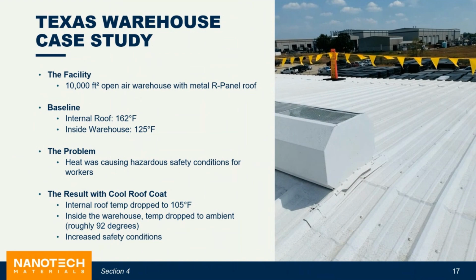Air temperature isn't what makes the warehouse miserable. A 162-degree Fahrenheit ceiling radiates onto workers the way a broiler does. You feel it on your head and your shoulders, regardless of what the wall thermostat says. That's why heat stress standards use wet bulb globe temperature, which includes a radiant measurement, rather than plain air temperature. Cutting the deck to 105 removes most of that radiant load, and this just improves working conditions for employees.